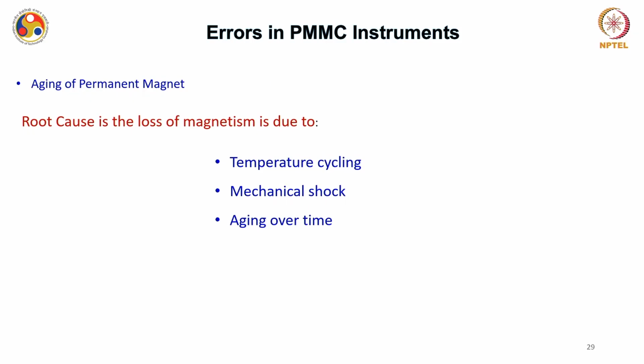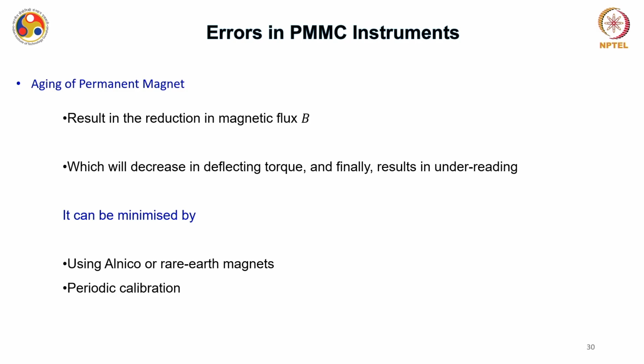The second error is because of the aging of the permanent magnet, which is quite obvious because continuous use of this permanent magnet, due to things like a temperature cycle or mechanical shock, can result in errors. This aging of the permanent magnet can result in a reduction in the magnetic flux B.